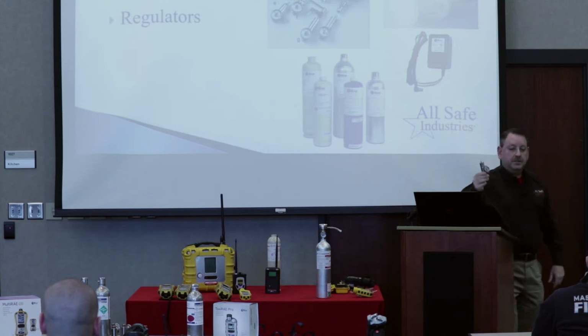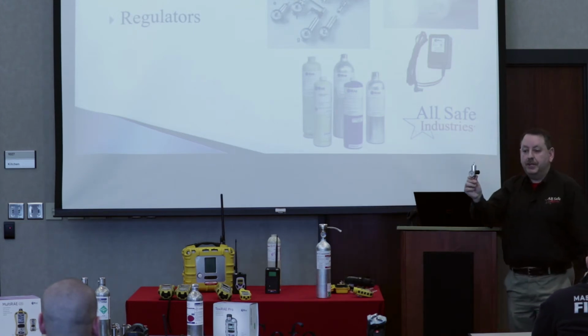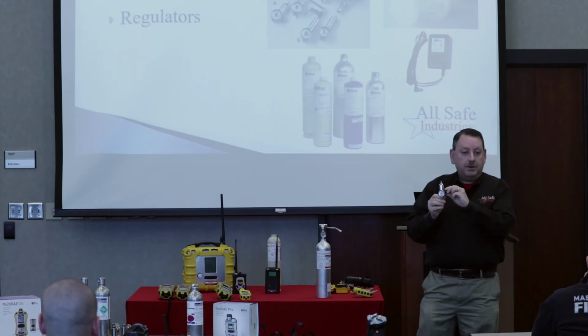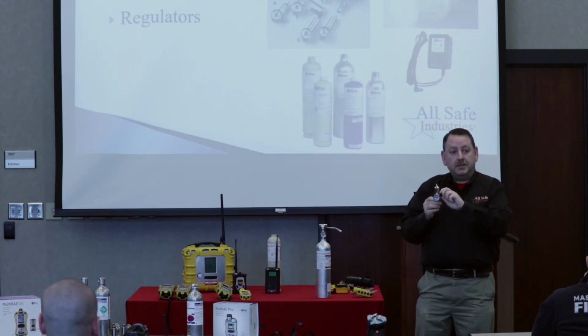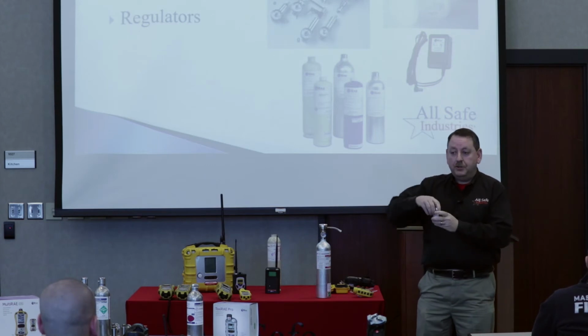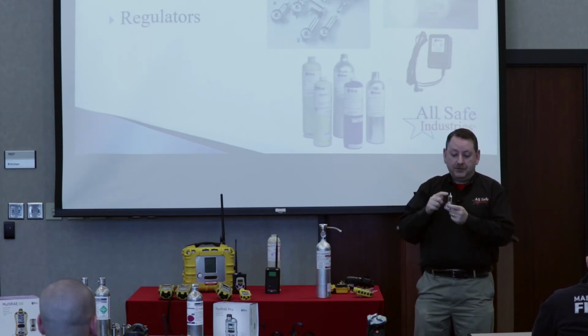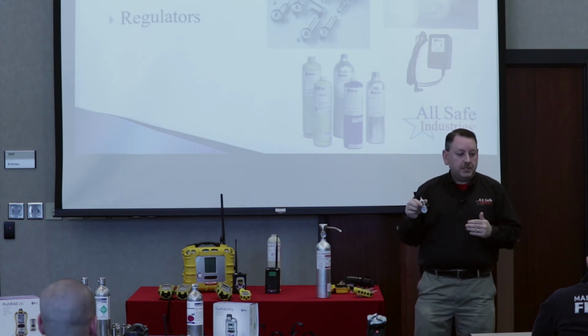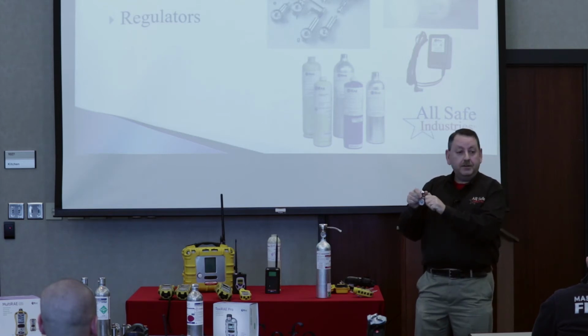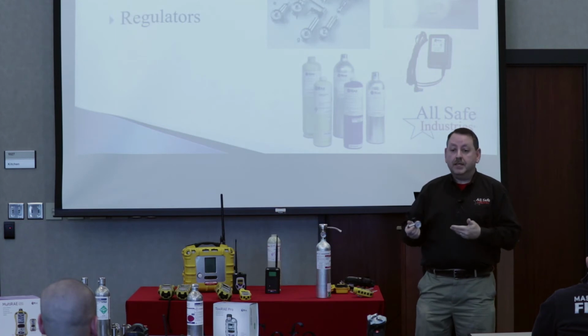This first one is what we call a preset flow rate regulator. It's the one that has the on-off knob on the side. So what we like to recommend is to keep the regulator open when you engage it into the cylinder. That way, if there's any gas trapped in here, it's not burping it into the cylinder. Once it's engaged and you hear the gas flowing, then you can shut it off. And then you just have it at the ready when you get your instrument into calibration mode, and when the meter says apply the gas, you turn on the regulator and it starts to flow gas to the instrument, and the calibration sequence will start. When you're done, obviously, turn this back off so we don't waste any gas.